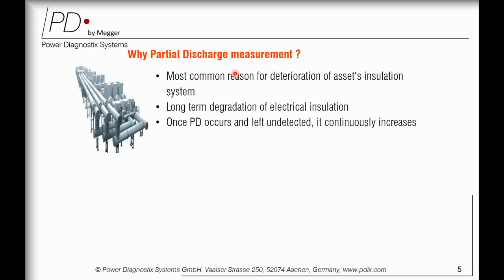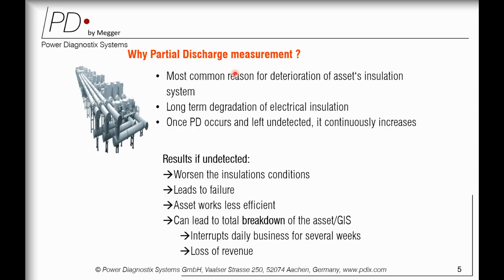long-term degradation of electrical insulation. Once you have PD and it is left undetected, it always increases over a period of time, because PD is just like cancer. Once we have it, it always gets bigger and bigger. Similarly in the GIS, once it has PD, it will keep getting bigger over a period of time. The result, if left undetected, is that the insulation condition leads to failure, the asset works less efficiently, and of course it leads to a total breakdown of the GIS asset.